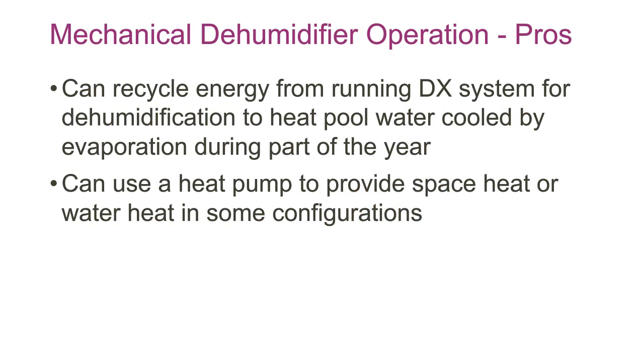On the plus side, the real plus is that you can heat some pool water with a mechanical dehumidifier. And when you look at energy loads, we're not going to talk about it greatly, but it's one of the four relatively significant components of energy, along with air distribution and fans, dehumidification, and ventilation, but air heating. In some configurations, you can use a heat pump to provide some space heat with these systems as well.